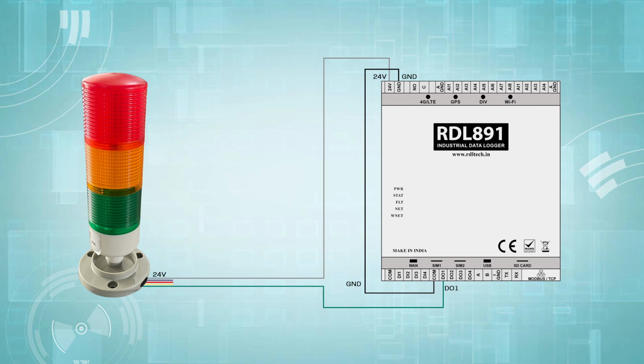First, let us see the connection diagram. Here, I am connecting the tower lamp to the data logger. The lamp's gray wire is for the 24 volts power supply, which is connected to the power supply positive terminal of the data logger. A common wire is connected to both the ground of the digital output and the power supply ground of the data logger, ensuring that both receive a 24 volts power supply.